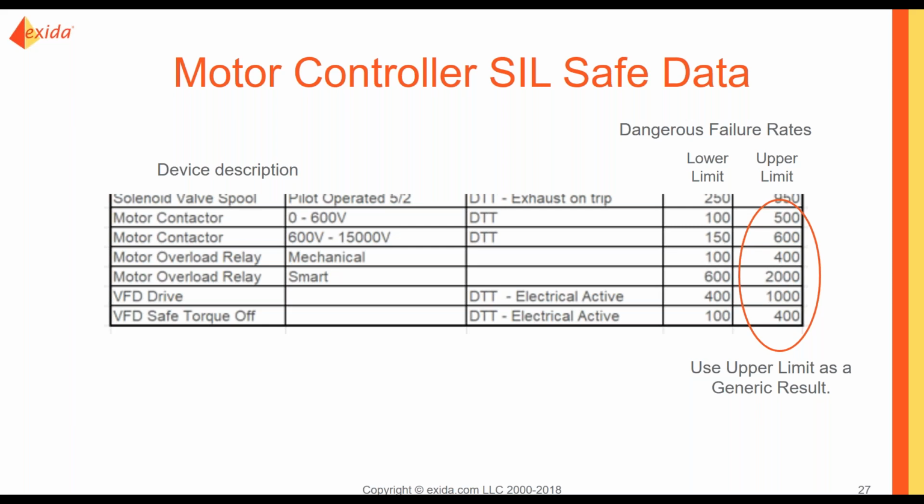So if I could real quickly recap, I just want to reiterate the fact that there is a misnomer out there right now, and we're seeing this come through a lot, where people are thinking that they're using certified equipment in their systems, not realizing that even though it says it's a 61508 certificate, SIL 2 or SIL 3 capable, even SIL 1 capable, those numbers came from the machine industry, and it's for a high demand and continuous certificate. And that is a huge difference there.